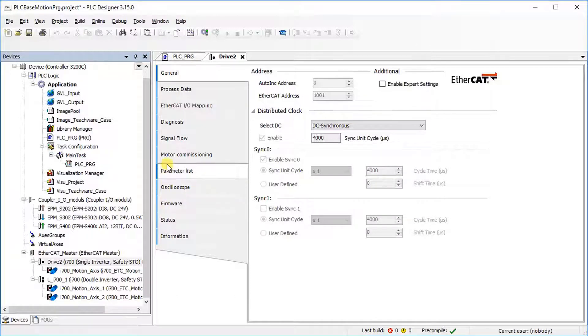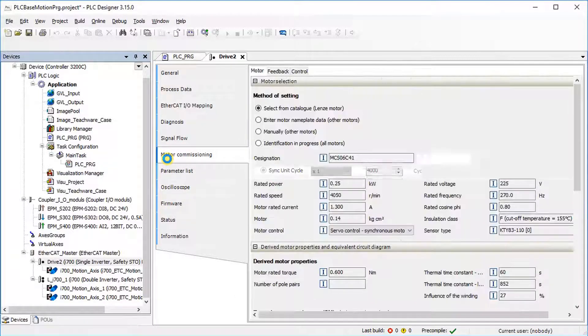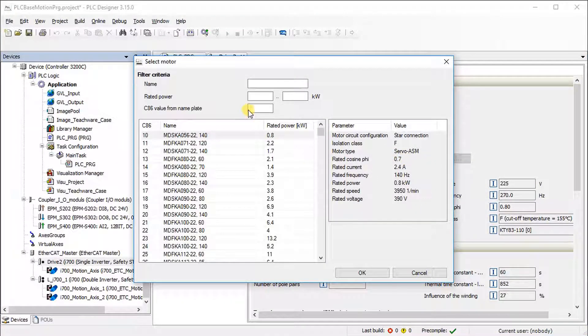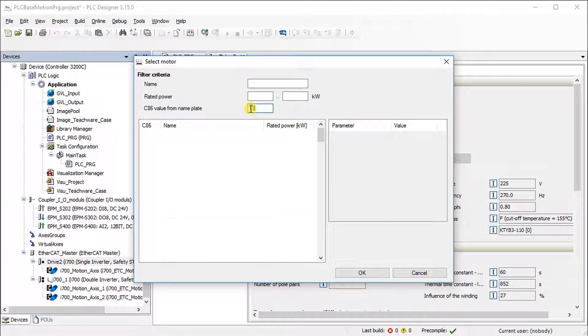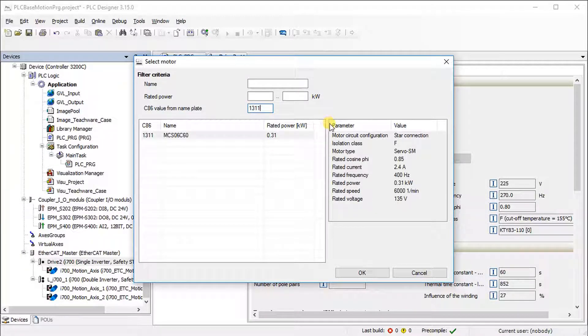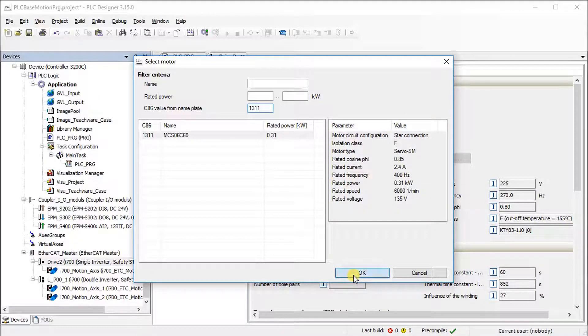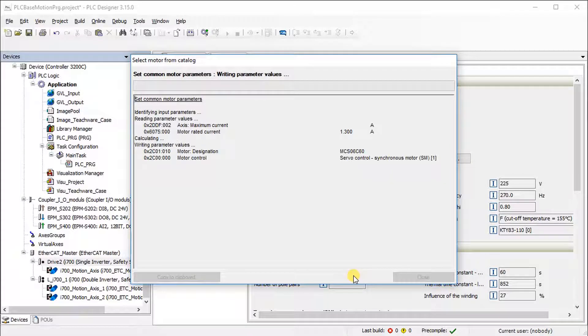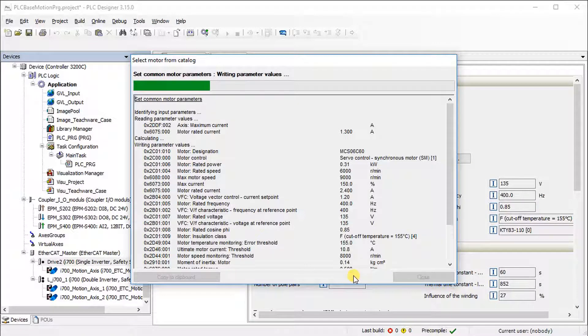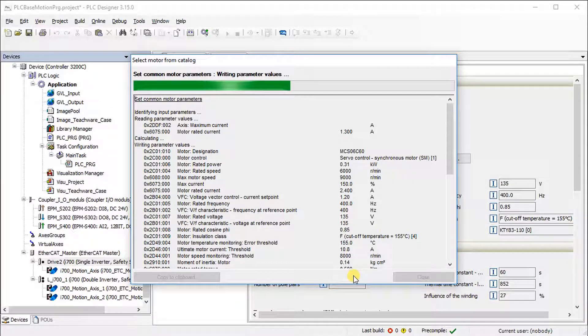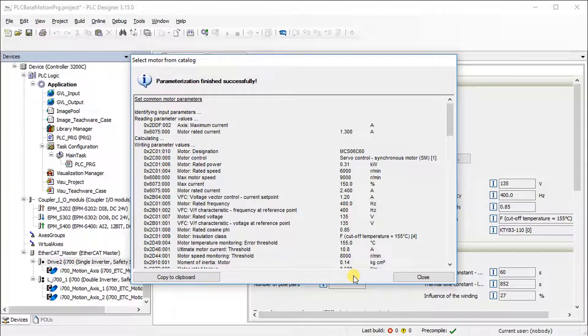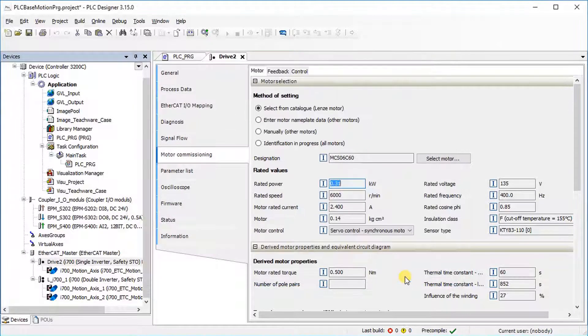Go to the Motor Commissioning tab. Press the Select Motor button. Enter the C86 code value from the motor nameplate, for example 1311. On the right side, some of the motor nameplate data are shown. Press the OK button to accept the motor data. Press the Close button after completion of the automatic motor data parameterization.